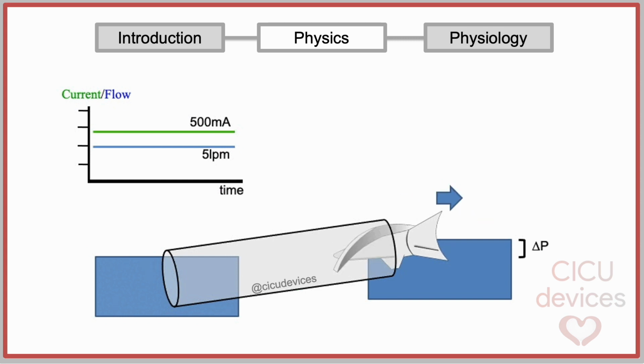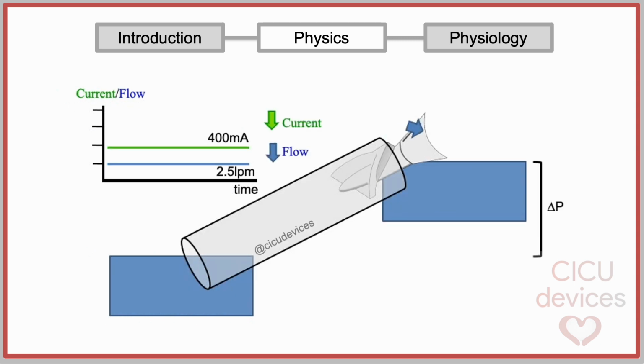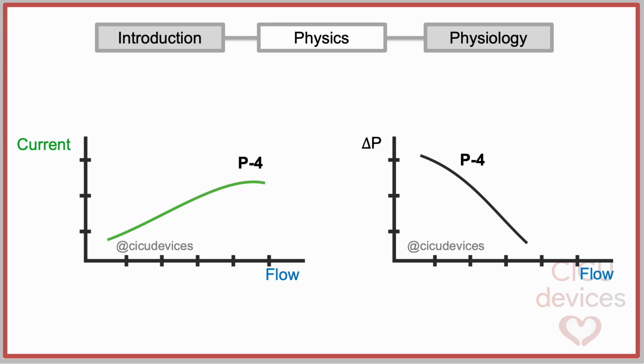If the pressure difference is low between inlet and outlet, then the flow is high and the power or current used to displace this amount of liquid will also be high. On the contrary, if the pressure difference between the inlet and outlet is high, the flow will be low, and the required power will be low too. In these graphs, we can observe the relationship between current and flow, and between pressure difference and flow for a specific rotational speed, or P level.